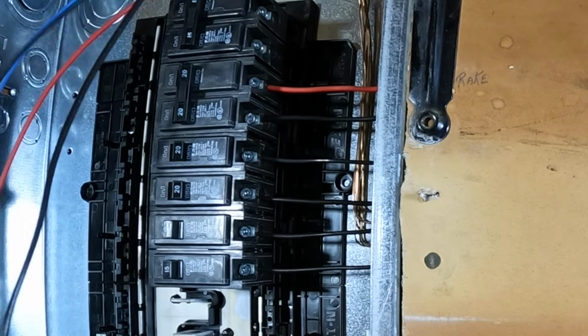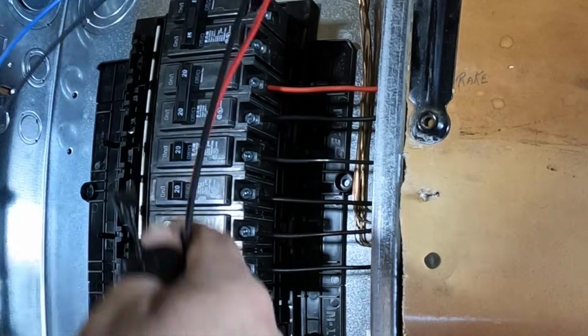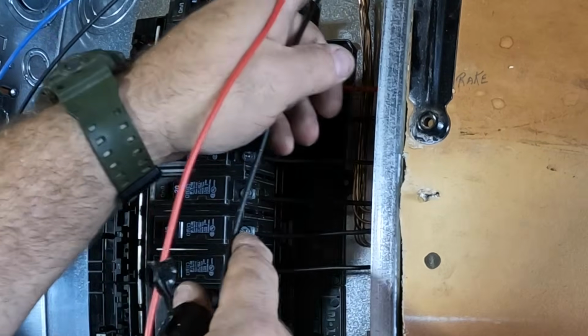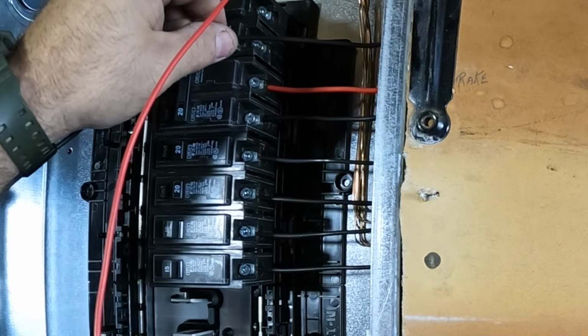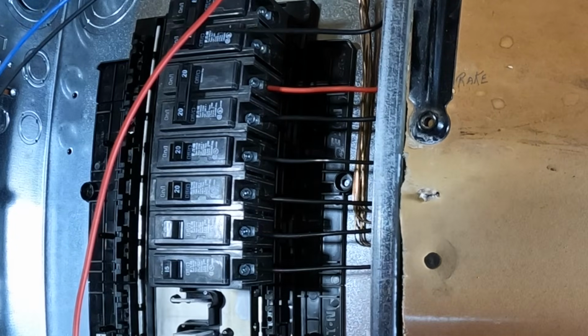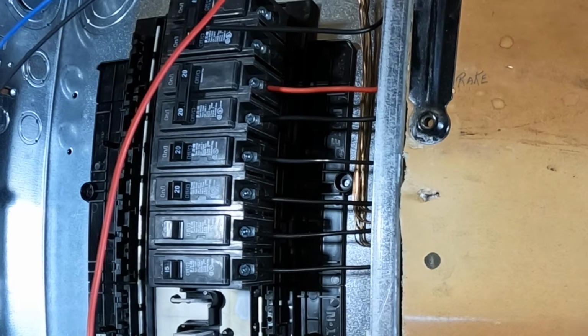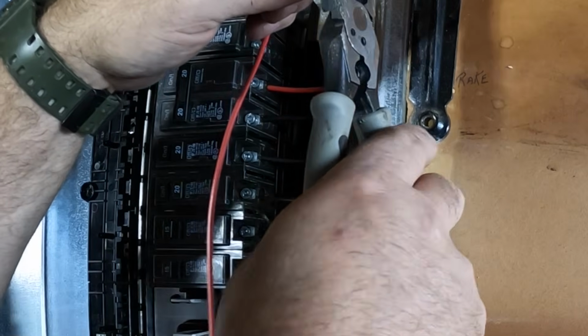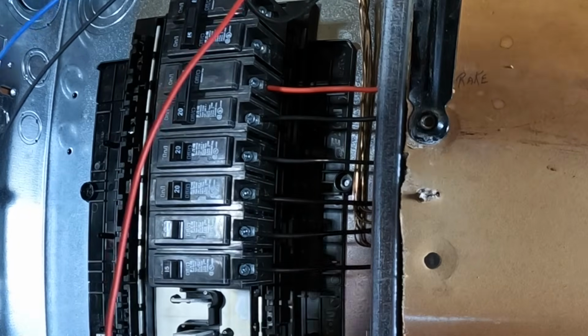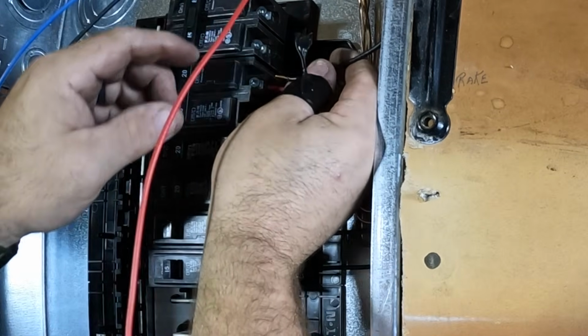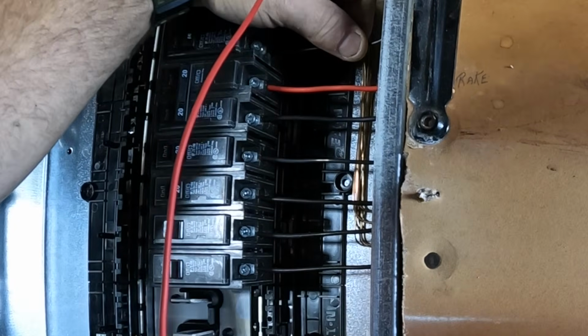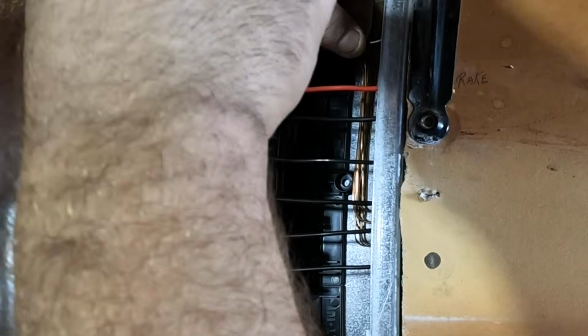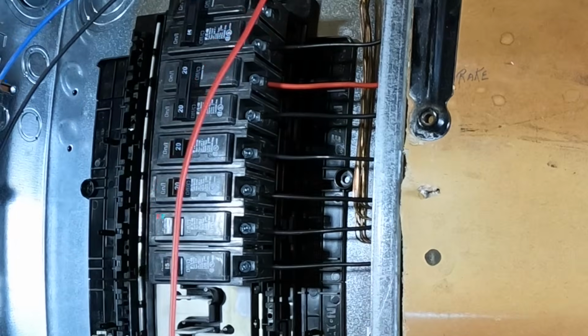Terminating these conductors, just do it nice one at a time. Single poles, double poles. One of the things we definitely have to do now when we have a multi-wire branch circuit, and I had a few in here, they have to terminate on a common trip circuit breaker. So what that means is when you have a 3-wire circuit, you're going to have amperage on both of your live conductors, the red and the black, and also on your neutral. The neutral is going to carry the imbalance between the black and red in a multi-wire branch circuit situation.